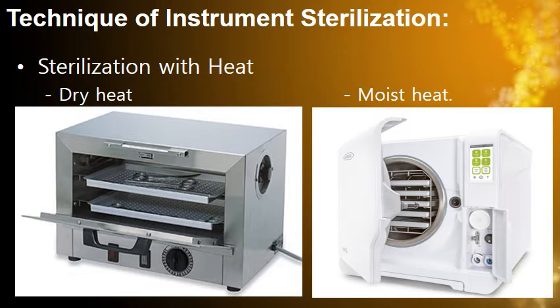And the other principle that the work of moist heat is based on is that it takes approximately several times as much heat to convert the boiling water to steam, which causes the steam that rises to have more heat, so it will kill faster. When the steam comes in contact with an object, the steam will condense and instantly release the stored heat energy, which will cause denaturation of the cell protein.